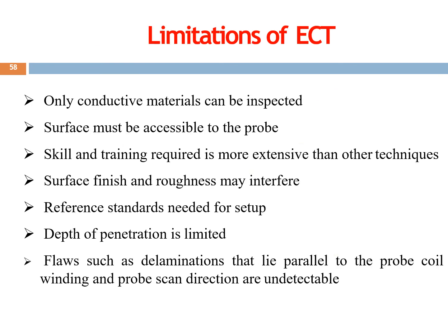Now we move on to the limitations. One of the major limitations is that only conductive materials can be inspected. The surface must be accessible to the probe, right? That is, we have to place the probe on the surface, so that must be done. Skill and training is required, more than for the other techniques. That is, we require more skill and training to do this technique compared to the other ones.